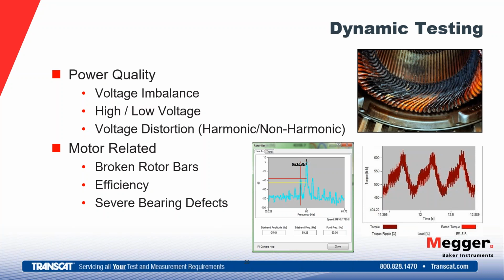Dynamic testing is going to help us, again, assess the environment of the motor, where it lives. We're going to assess that power quality: voltage imbalance, high or low voltage. We'll set parameters there, thresholds, usually set at 10% for high and 5% under for low-end voltage, and voltage distortion. Especially voltage imbalance and voltage distortion are causing currents that are circulating in the opposite direction from what we need. So it's working against that motor. The motor actually has to slow the rotor some more in order to produce the same amount of torque that was required if it had perfect power.